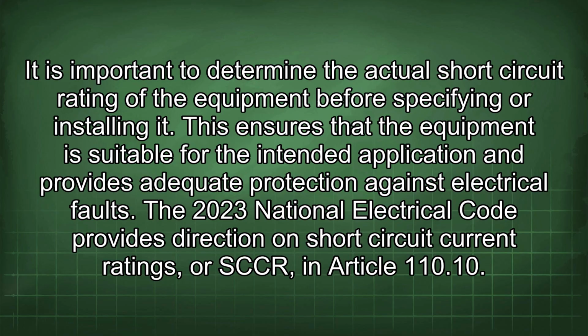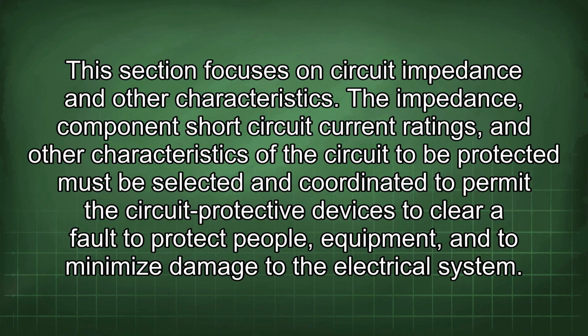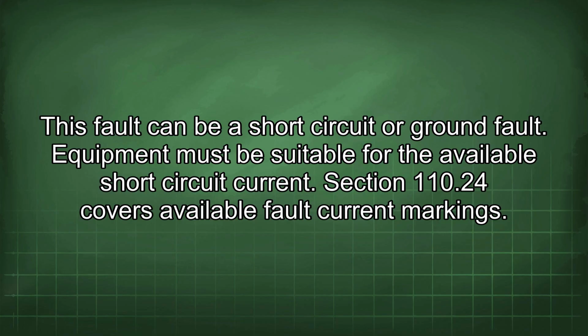The 2023 National Electrical Code provides direction on short-circuit current ratings, or SCCR, in Article 110.10. This section focuses on circuit impedance and other characteristics. The impedance, component short-circuit current ratings, and other characteristics of the circuit to be protected must be selected and coordinated to permit the circuit protective devices to clear a fault to protect people, equipment, and to minimize damage to the electrical system. This fault can be a short circuit or ground fault. Equipment must be suitable for the available short-circuit current.